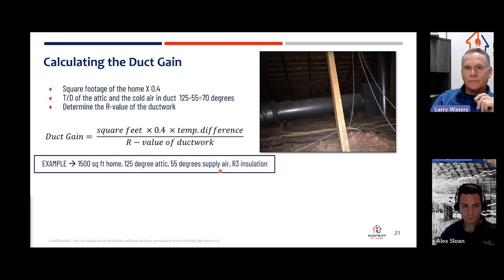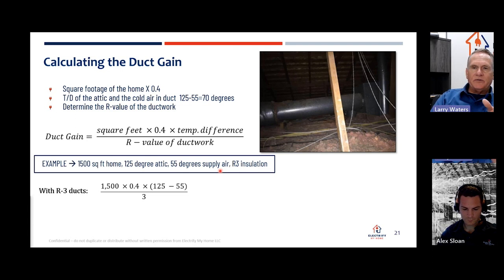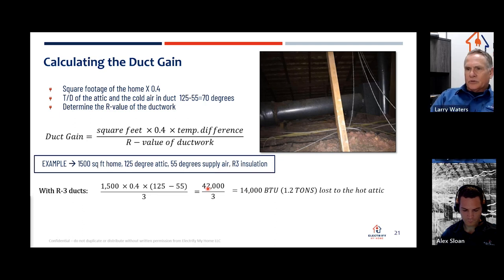Okay, so let's do the math on this. So with R3 ducts, I'm going to take the 1,500 square foot house times 0.4. That is going to give us our internal surface area. We multiply that by the temperature difference, which is 125 to 55. That's going to be a 70 degree temperature difference. And we divide that by our R value. So we take 1,500 times 0.4 times the 70 degree temperature difference. That's going to give us 42,000. We divide that by 3. So that's 14,000 BTUs, 1.2 tons of cooling capacity that's being lost to the hot attic space.